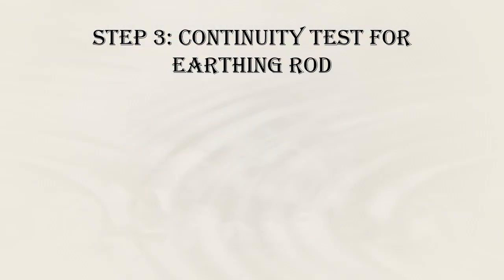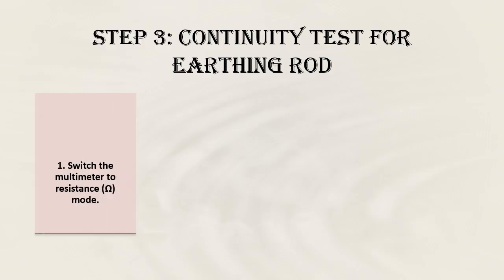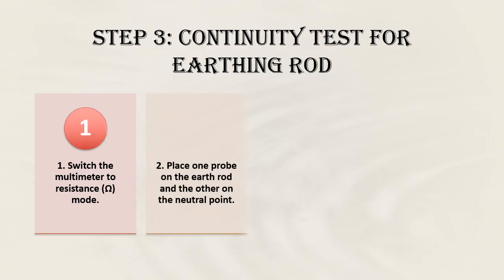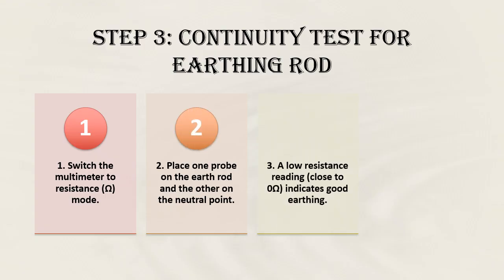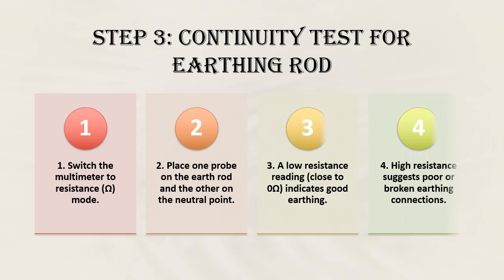Step 3: Continuity test for earthing rod. For outdoor or industrial systems, you can test the earth rod directly. Switch your multimeter to resistance mode. Place one probe on the earth rod and the other on the neutral point. A reading close to 0 ohms means good earthing, while higher resistance indicates poor or broken connections.